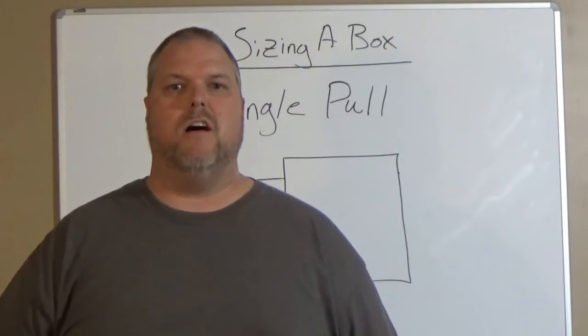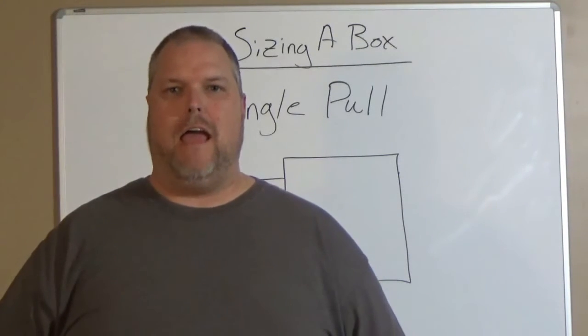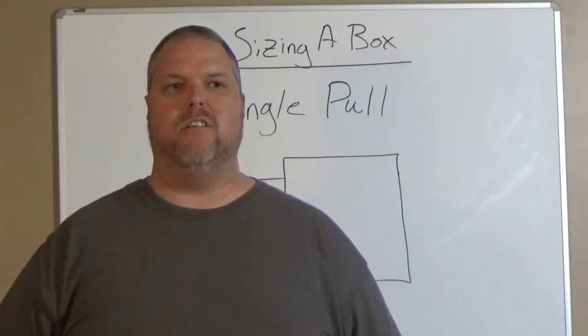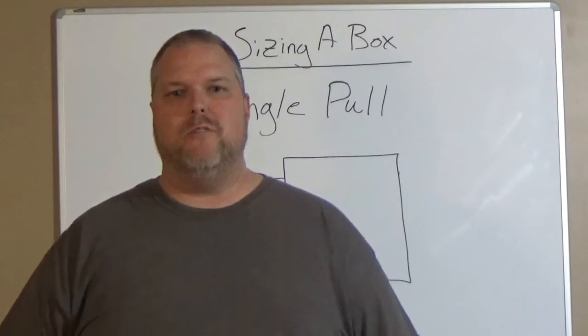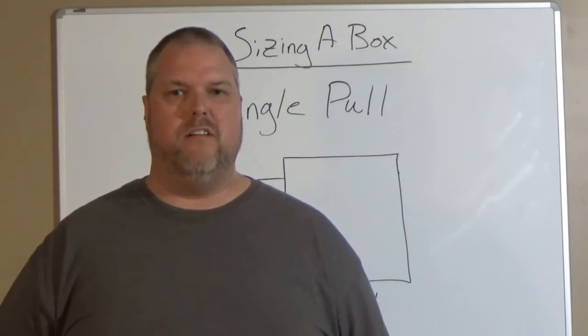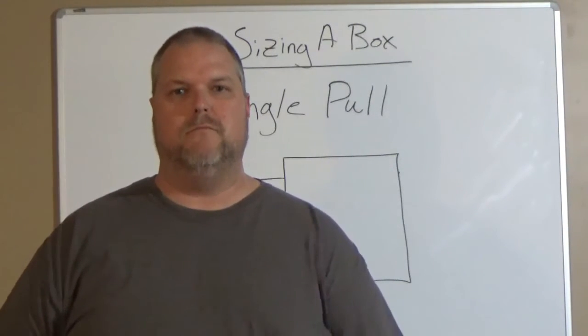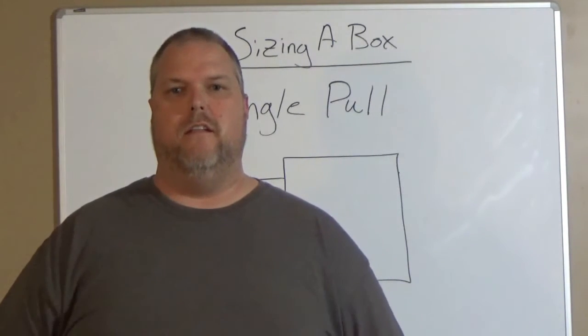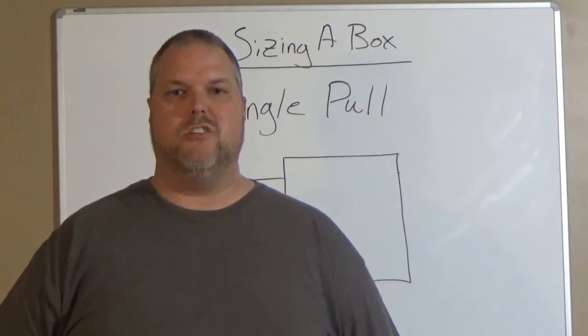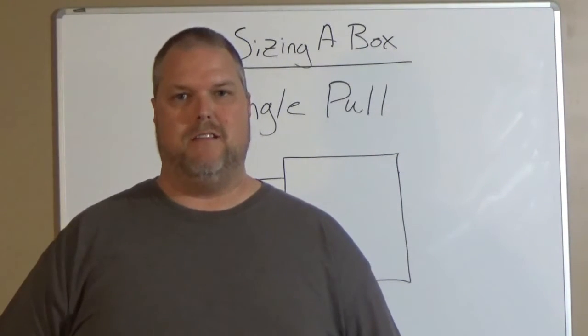We are going to now discuss Article 314.28A2, which covers angles and U pulls. How do we size a junction box? Very simple. You have to remember two rules. If it's a straight through pull, you're going to multiply the largest conduit by 8. In an angle pull, you're still going to multiply the largest conduit, but instead of multiplying it by 8, you're going to multiply it by 6.